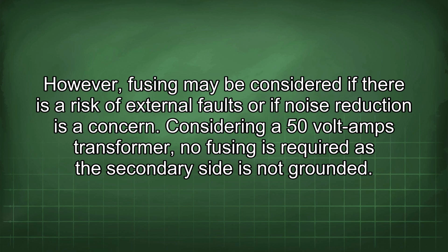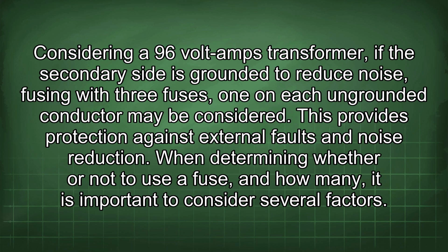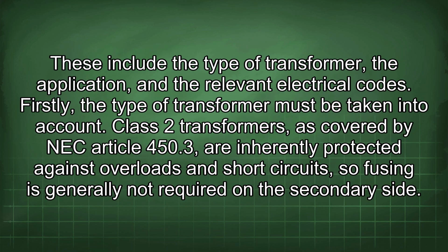Considering a 50 volt amps transformer, no fusing is required as the secondary side is not grounded. Considering a 96 volt amps transformer, if the secondary side is grounded to reduce noise, fusing with 3 fuses, one on each ungrounded conductor, may be considered. This provides protection against external faults and noise reduction. When determining whether or not to use a fuse and how many, it is important to consider several factors. These include the type of transformer, the application, and the relevant electrical codes.